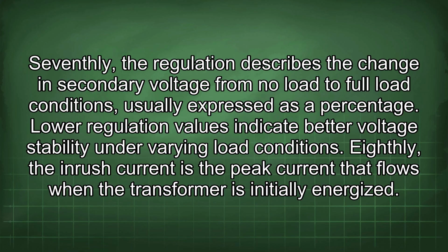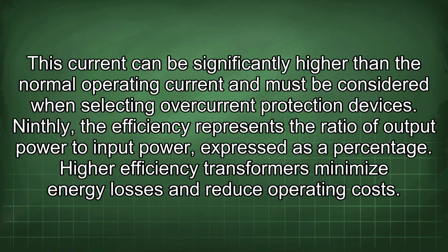Eighthly, the inrush current is the peak current that flows when the transformer is initially energized. This current can be significantly higher than the normal operating current and must be considered when selecting overcurrent protection devices. Ninthly, the efficiency represents the ratio of output power to input power, expressed as a percentage. Higher efficiency transformers minimize energy losses and reduce operating costs.